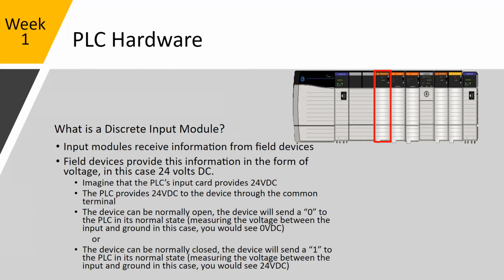The device can be normally open. The device will send a 0 to the PLC in its normal state. It measures the voltage between the input and the ground on the case, and you will see 0. The device can be normally closed, and the device will send a 1 to the PLC in its normal state, meaning the voltage between the ground and the case is 24 volts.